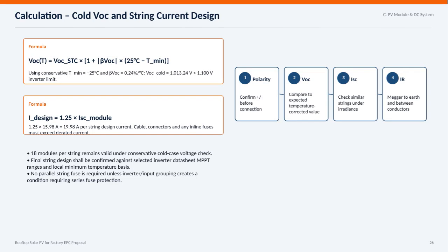Here we focus on the calculation of cold VOC and string current design, which are crucial for ensuring the safety and efficiency of the PV system. First, we use the formula: VOC at temperature equals the standard test condition VOC multiplied by 1 plus the absolute value of the temperature coefficient times the difference between 25 degrees Celsius and the minimum temperature. Using a conservative minimum temperature of minus 25 degrees and a temperature coefficient of 0.24% per degree Celsius, the cold VOC calculates to 1013.24 volts, which is safely below the 1100 volt inverter limit.